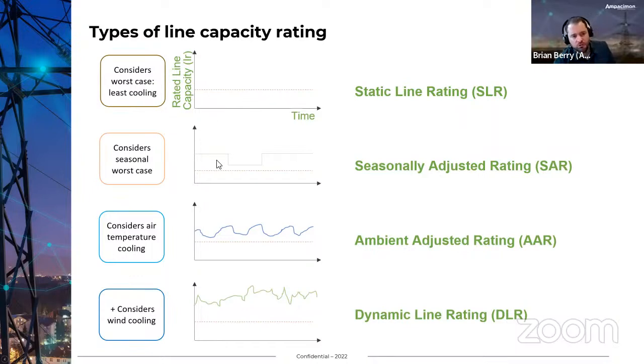But we all know winter's cold and summer's hot. So if I assume something that came from a factory rated at 30 degrees Celsius, but I'm running this in Norway, which is cold all the time, surely I can push it a bit more. Well, that's where seasonal adjusted rating comes from. I work out my typical highest temperature in winter and the highest in summer, and every year in winter I push up higher ratings, and in summer I have lower ratings. That's seasonal adjusted.